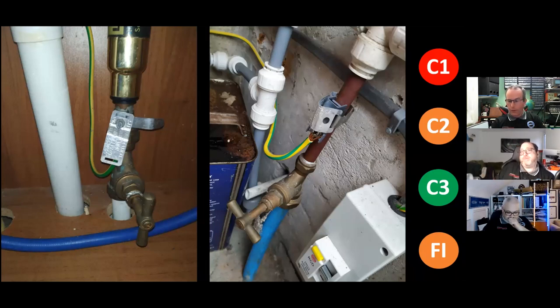All right, so we've got 41% FI for this one. So it's not a bad shout. And a couple of people will be commenting, I know, because I know who's in this room, that they'll be saying, well, it could go under the ground later on, some of the pipe work. So the metal pipe work that John's described for the left installation may go under the ground. Perfect place for a test required to see where bonding may be required, but not where they've done it. So FI, because that one on the left is metal for most of the rest of the property. You can't assume that it's actually just connected through that bit of plastic because it could go into other parts of the building or under the floor or who knows what.